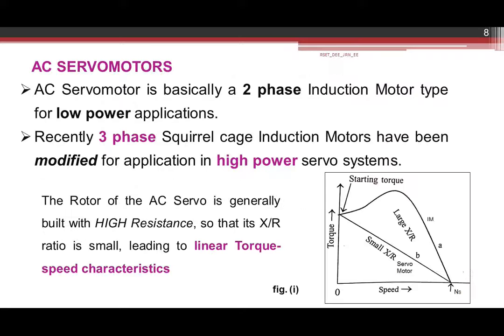It should have linear torque-speed characteristics — very essential. Output torque at any speed should be roughly proportional to the applied control signal, and stable operation without oscillations or overshoot is mandatory for a good servo motor. AC servo motor is basically a two-phase induction motor type for low power applications, but three-phase type is also present. The rotor of the AC servo motor is generally squirrel cage and should be built with high resistance so that the X/R ratio is small, leading to linear torque-speed characteristics.